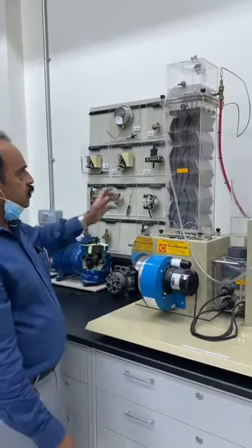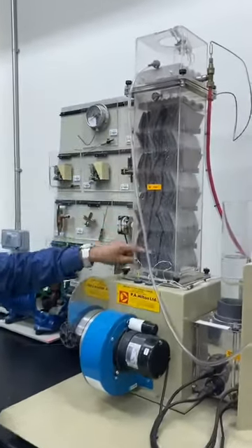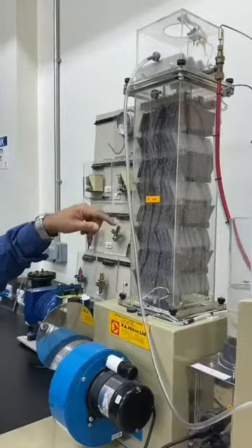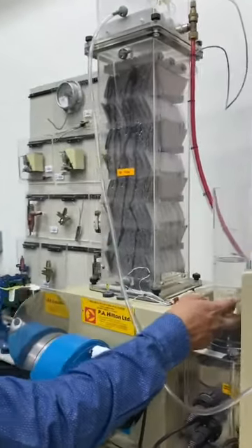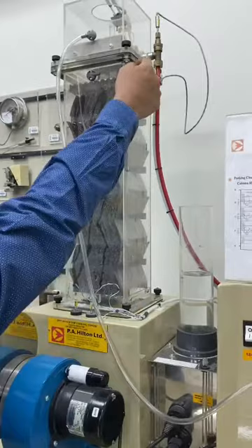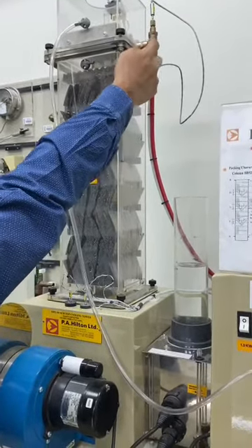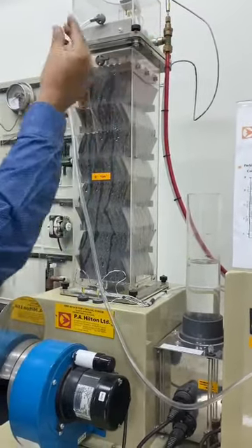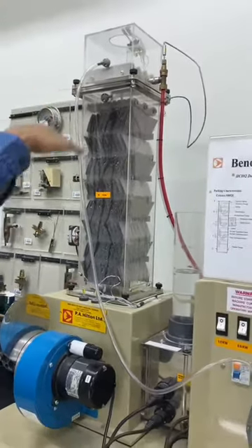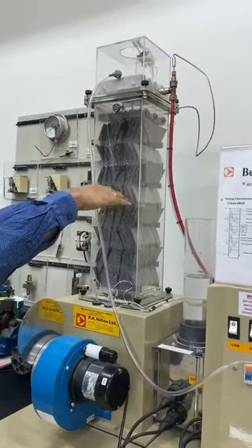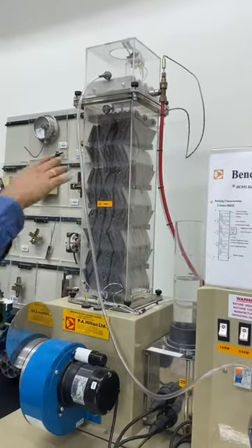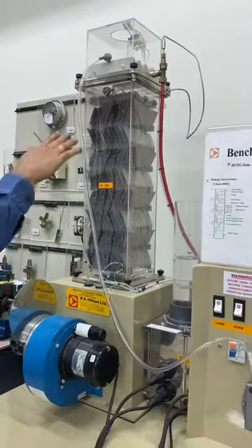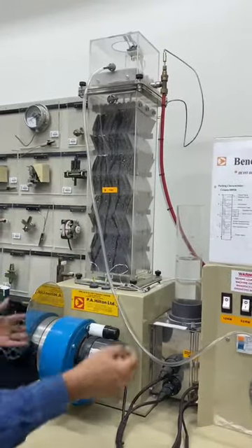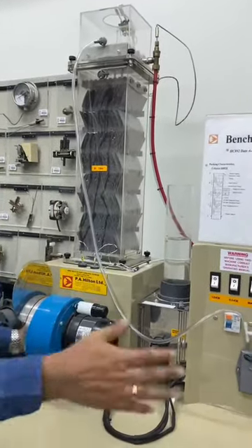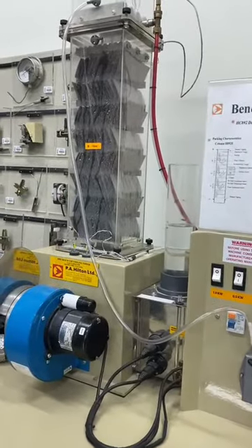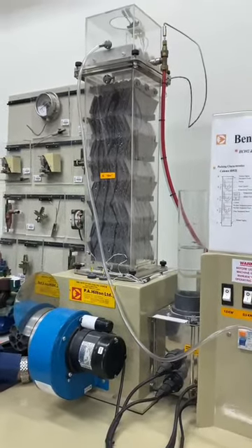And then there are fills. You can see the fills here. And here, this is the water. This water is pumped, and it is the hot water. This hot water is going to the pipe here, and in the pipe there are spray nozzles. That nozzle will spray hot water, and the air will cool the hot water, and the cold water will be collected at the base down. And it is used for condenser purpose, condensing the refrigerant in the condenser.